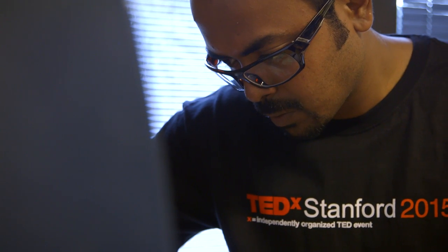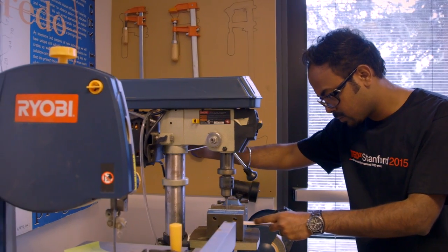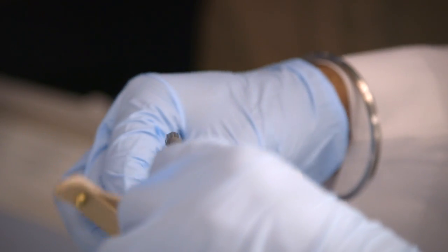When we saw that, we felt like, oh my god, this is a mechanical process. This is like hitting a nail onto the wall. If we can somehow measure the force that the physician is exerting in the process of screwing the lead inside the myocardium, it will give him feedback of how well the lead was anchored. And to solve that, we used a spring and two popsicle sticks.